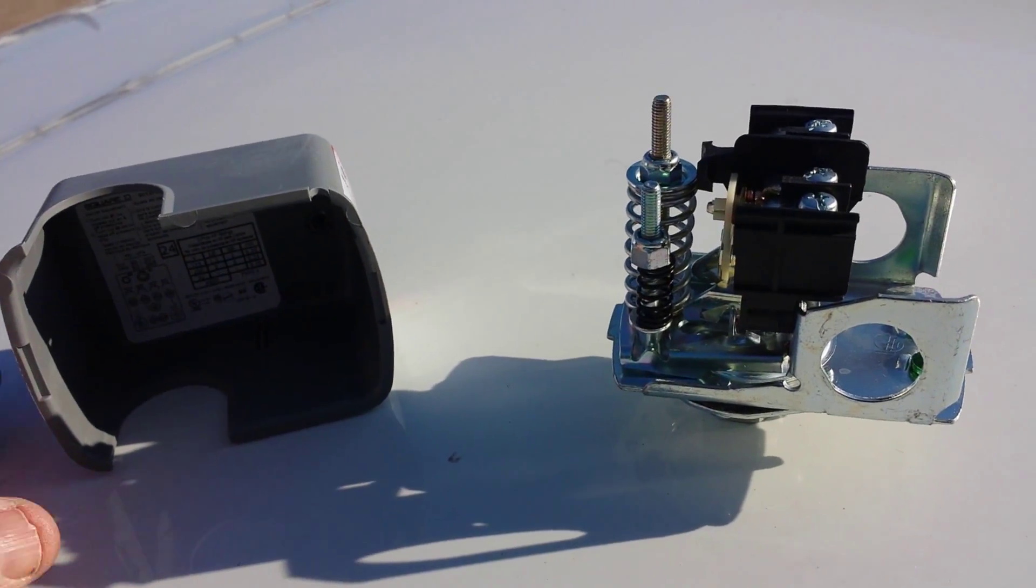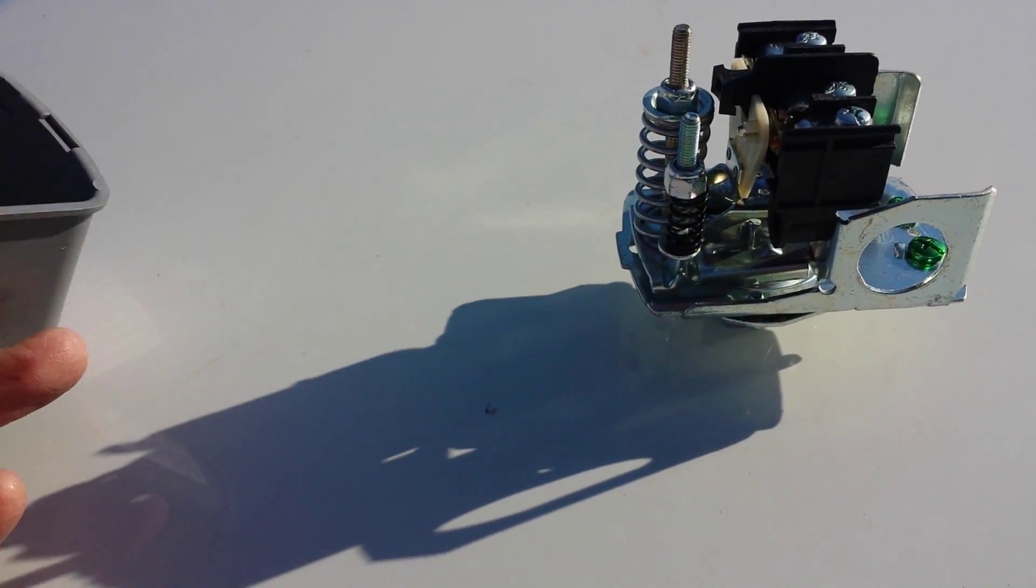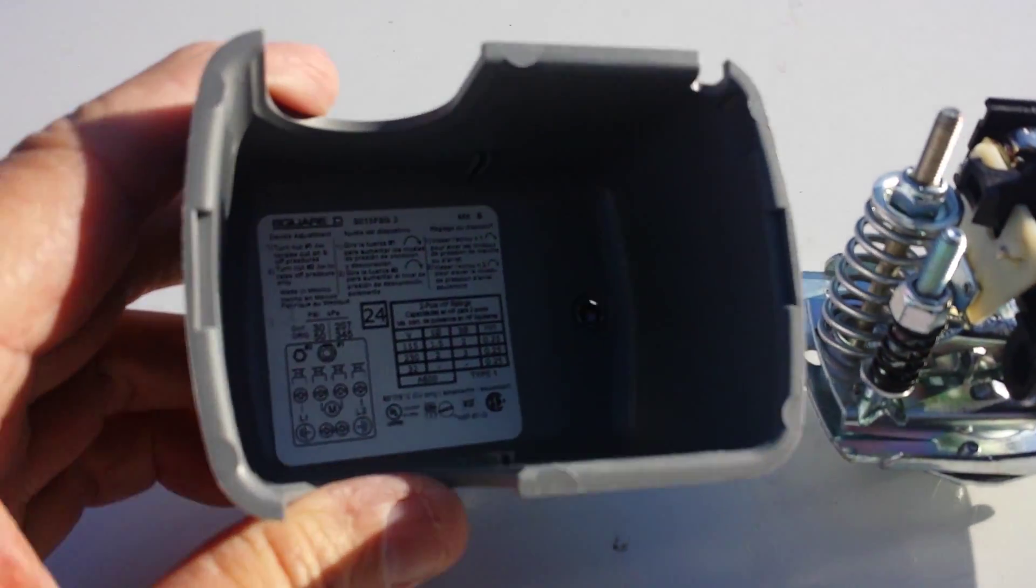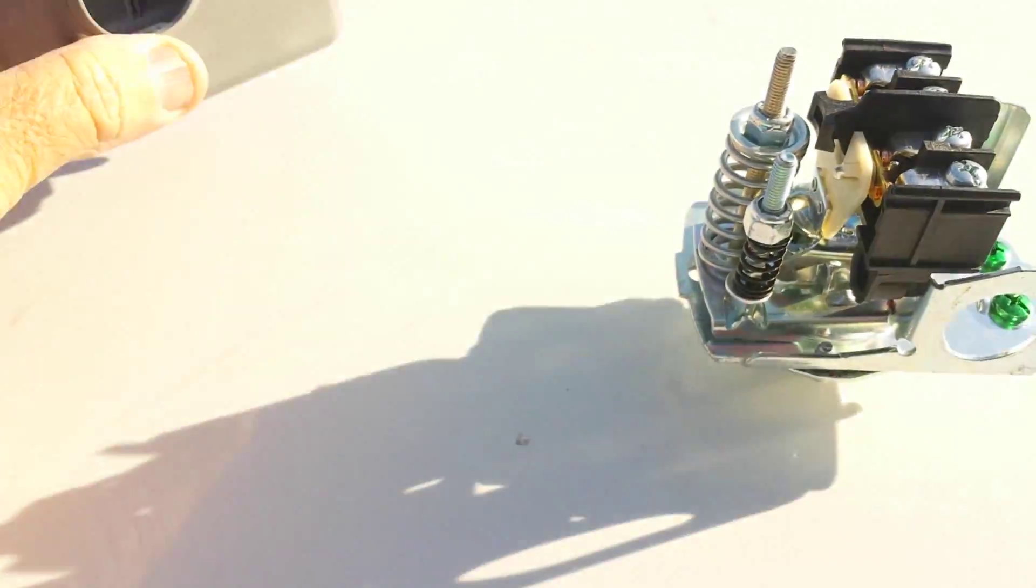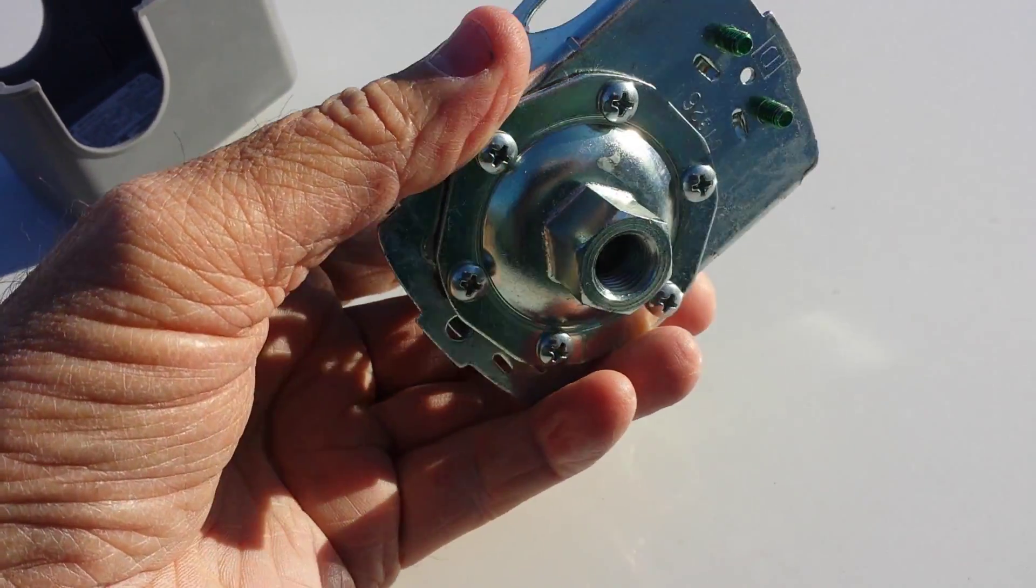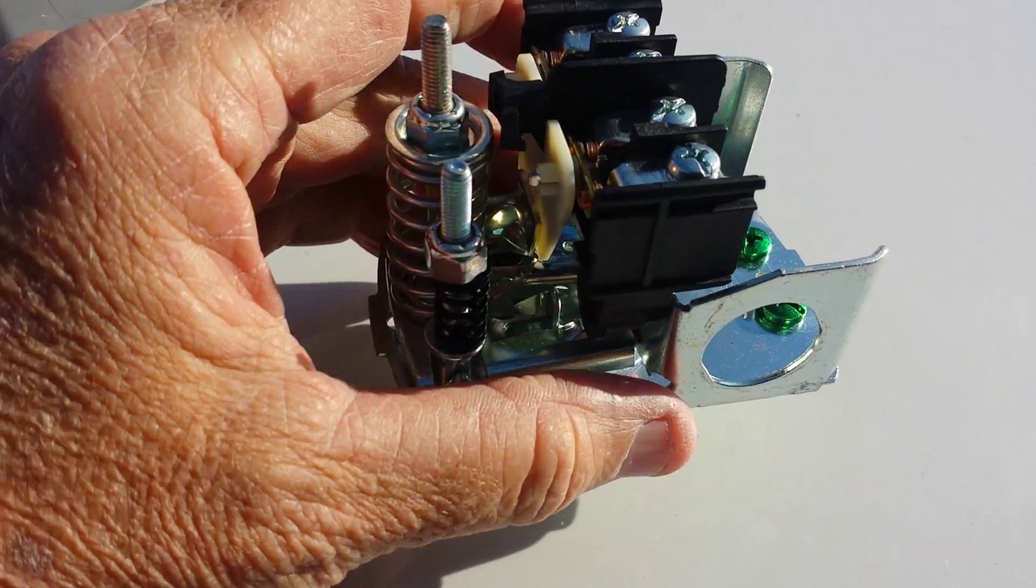Okay, everything you ever needed to know about your pressure control switch. This is a Square D brand 30/50 switch. You take the lid off and look inside the lid, and you'll see right here that it says on at 30 pounds, off at 50 pounds.